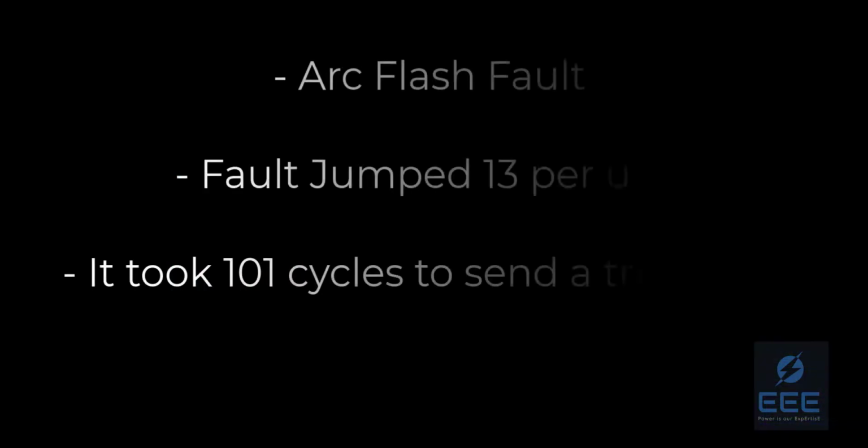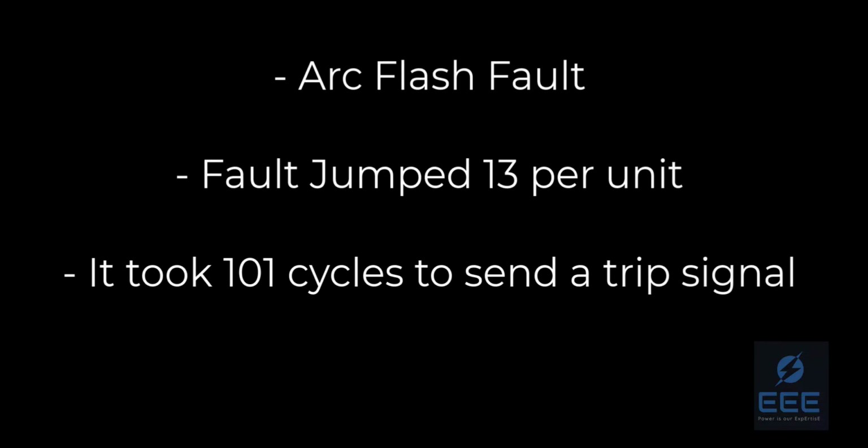An arc flash fault occurred at the primary zone of this relay. The fault current was 13 per unit. It took 101 cycles for the relay to send the trip.